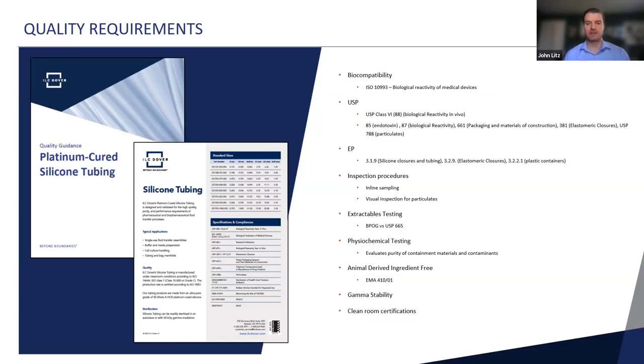It's also very important that your supplier have good inspection procedures when it comes to tubing extrusion. So you're going to want to make sure that there's some kind of inline sampling done to ensure the tubing is within its specified tolerances: ID, OD, length, wall thickness, etc. Visual inspection for any type of particulates, right? So at ILC Dover, we do 100% visual inspection over a light box. So our operators can see that there is no visible or subvisible particulate in the packaging or in the tubing itself.